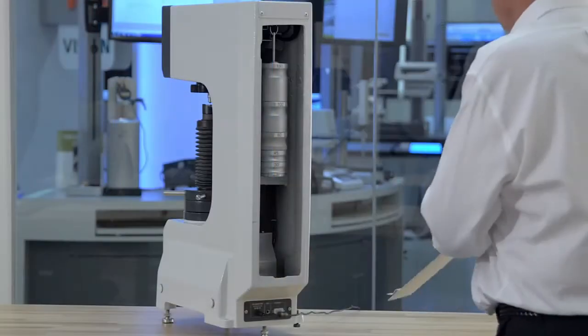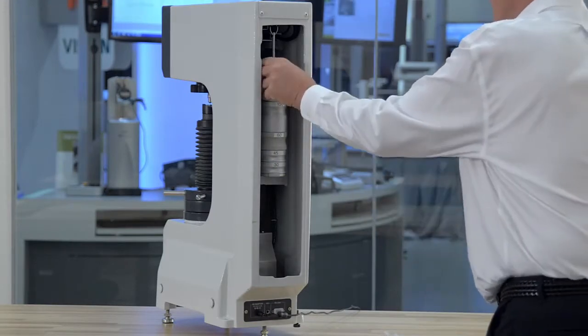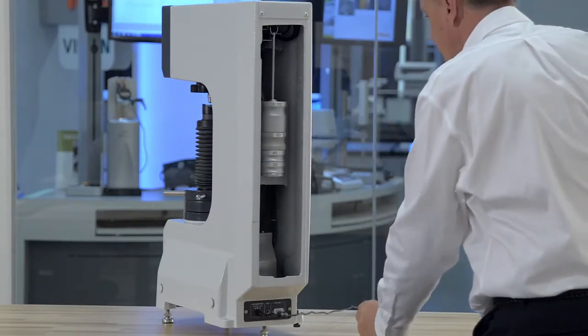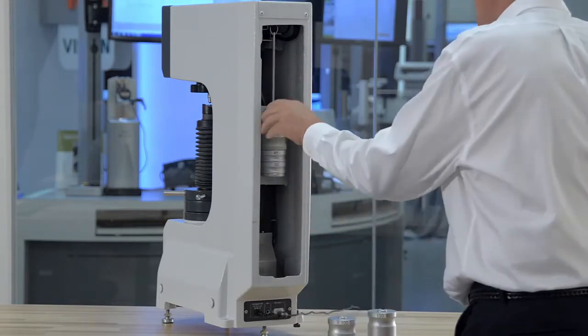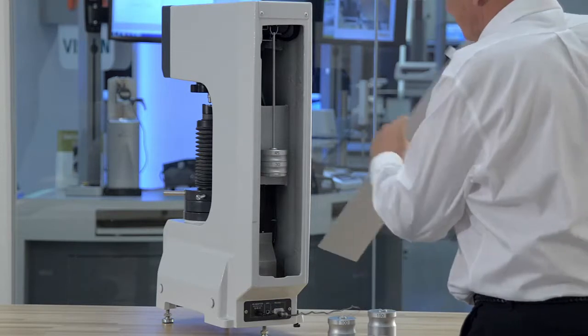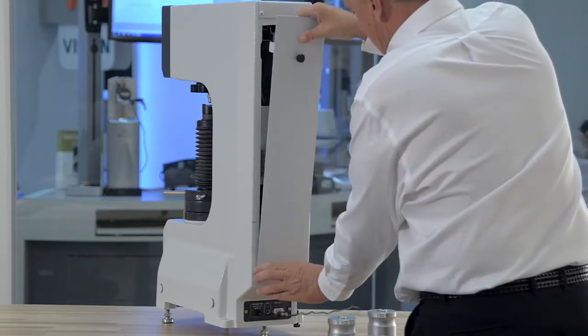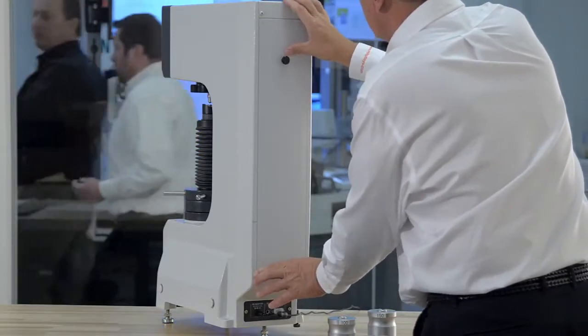Its twin tester design allows the operator to test on all 15 Rockwell scales and all 15 superficial scales when optional indenters are used. The adjustable hanging weight system is used to keep costs down and is a good option when you need a highly versatile tester for future testing requirements.